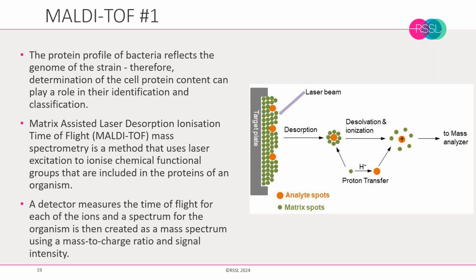So MALDI-TOF is an initialism for a fairly longish phrase, which is matrix-assisted laser desorption ionization time of flight. And normally after MALDI-TOF, we also get the initials MS, and MS is for mass spectrometry. And the basis of the technology is to use laser excitation to ionize chemical functional groups that are part of the protein makeup of an organism.